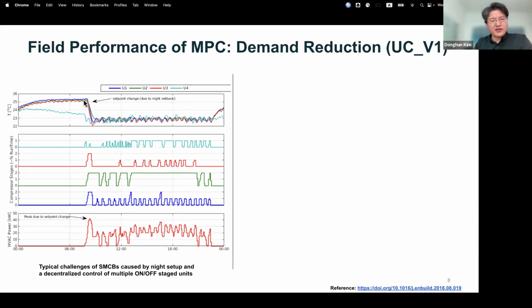You can see during summer, the temperature goes very high, and once the occupied period starts, due to the termination of the night setback, the set point lowers and temperature reduces very dramatically. Because of this night setback, we believe it's much more energy efficient, but it kicks in and all the RTUs have to run at full speed, showing a peak power. This is only 4 RTUs, but imagine buildings with 30 RTUs - this peak is huge. There's also an unnecessary peak, coincidentally happening because of the decentralized control nature of the current thermostat-based control - we cannot prevent this problem.